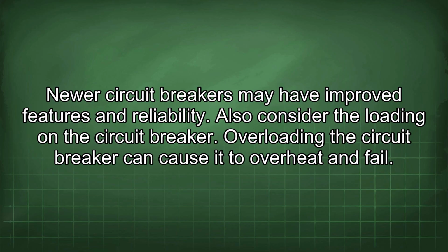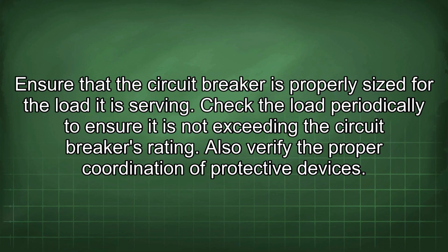Also consider the loading on the circuit breaker. Overloading the circuit breaker can cause it to overheat and fail. Ensure that the circuit breaker is properly sized for the load it is serving. Check the load periodically to ensure it is not exceeding the circuit breaker's rating.